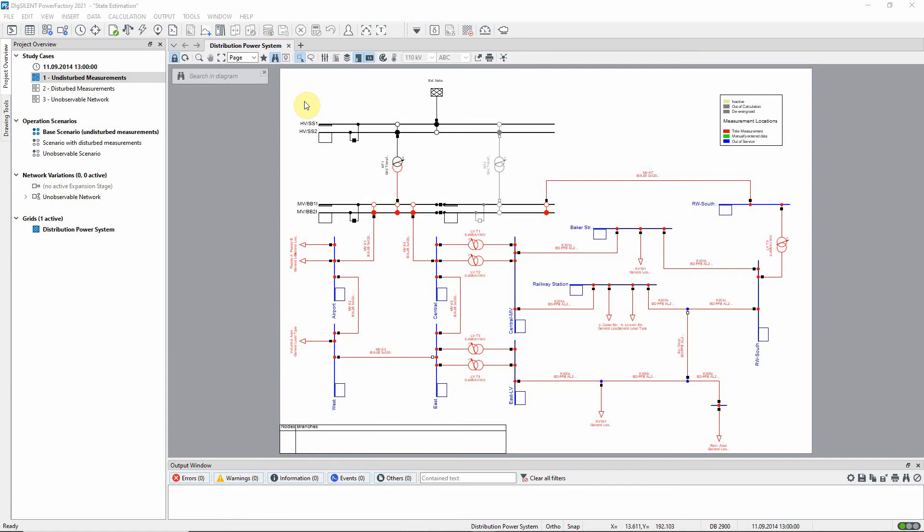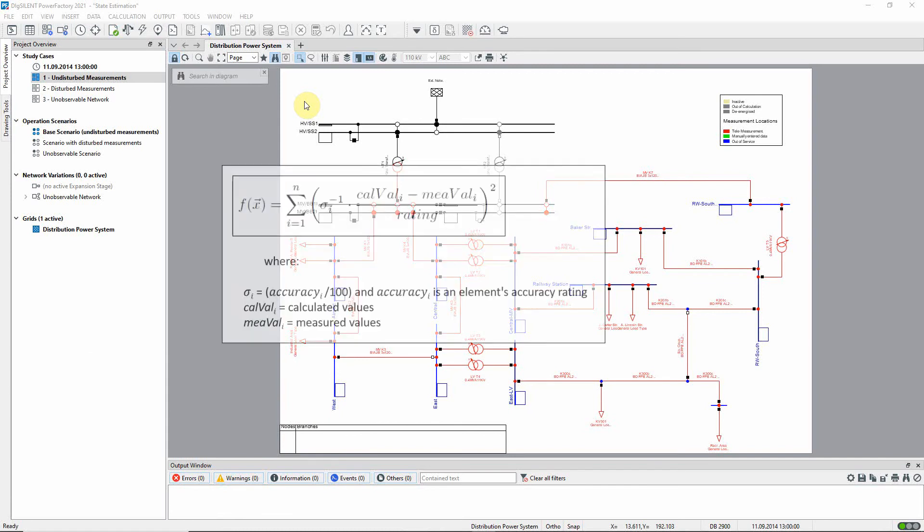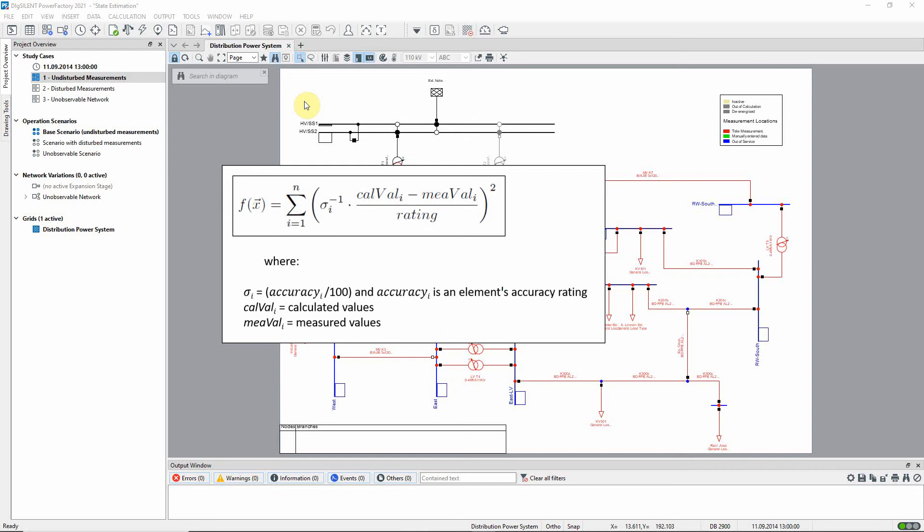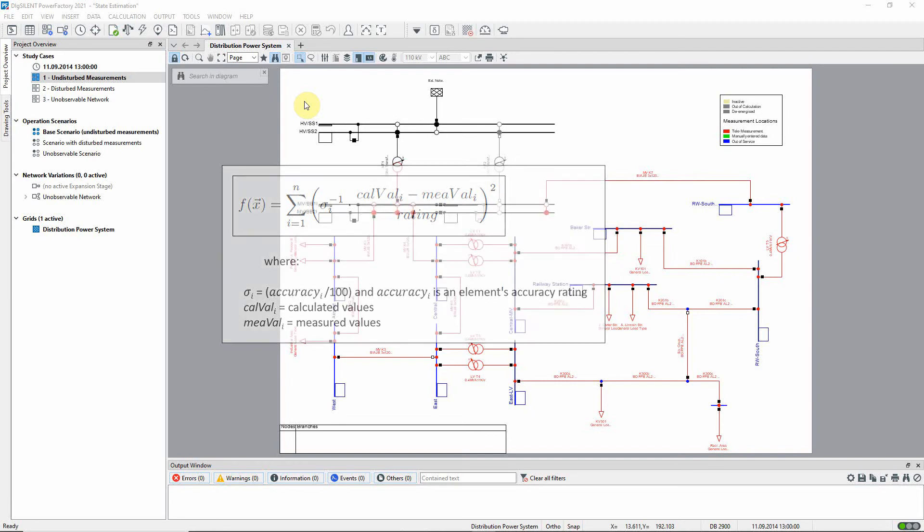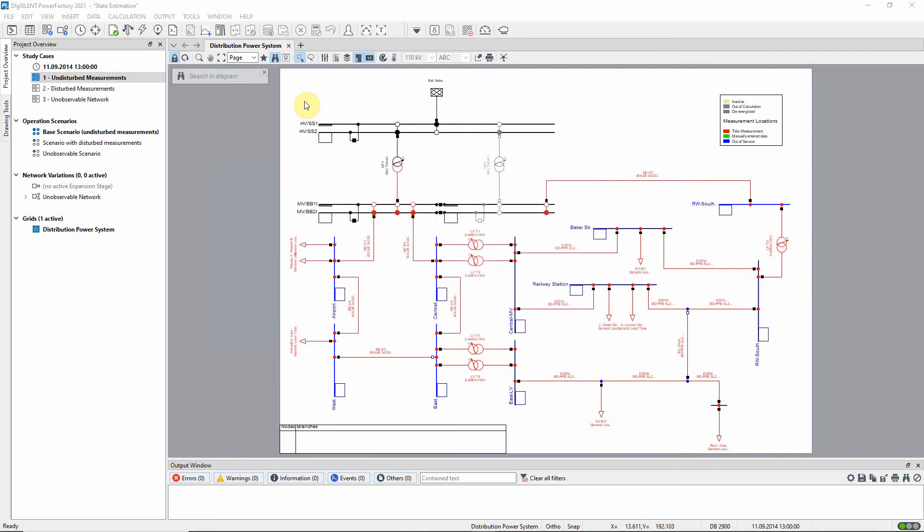At the core of the function is an optimization process whose objective is to minimize the difference between the calculated load flow results and the measurement values through adjustment of the relevant element attributes. The state estimation function then provides the user with detailed reporting which can be used to identify areas where improvements are required because the measurement results are insufficient or of poor quality.